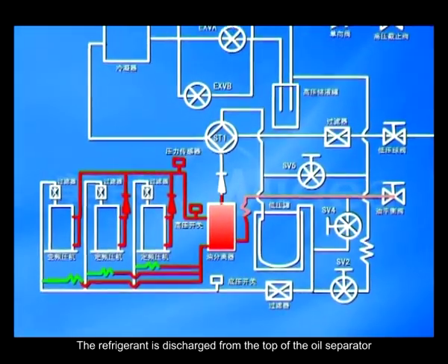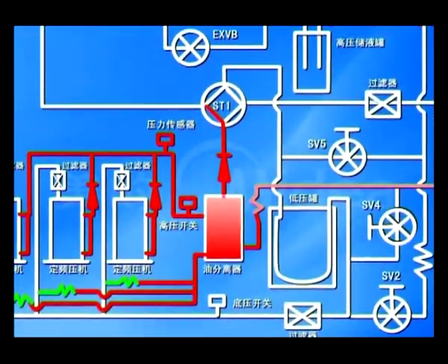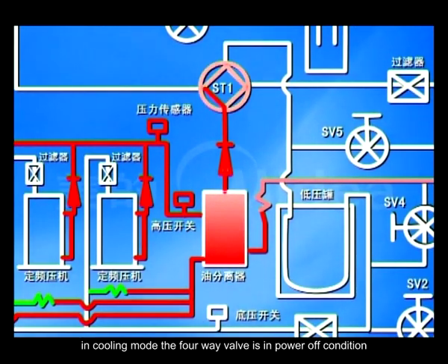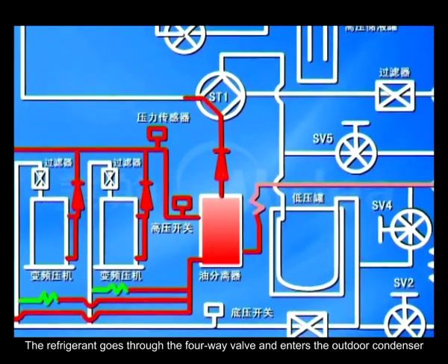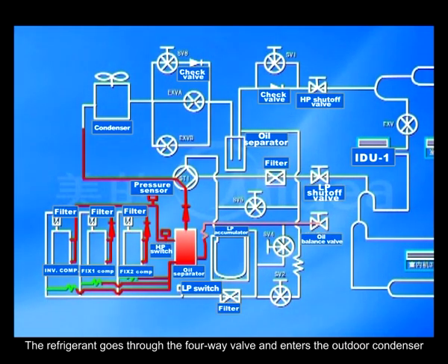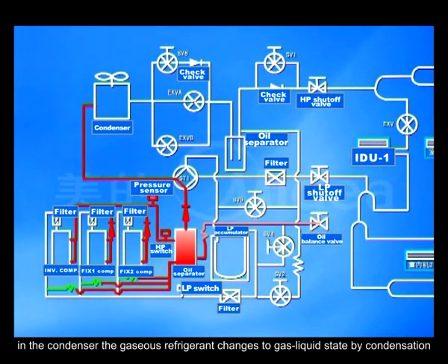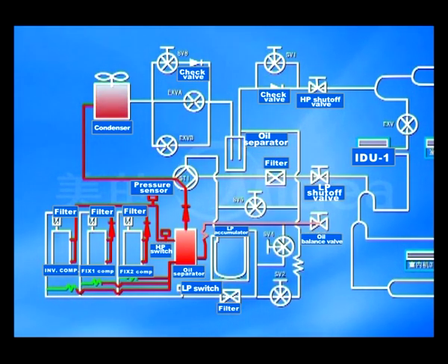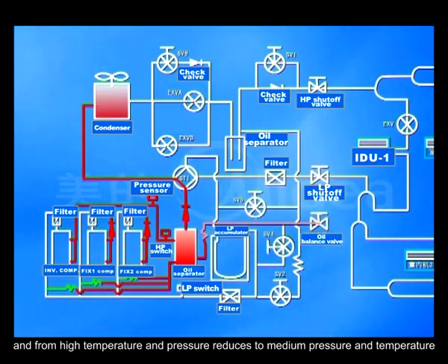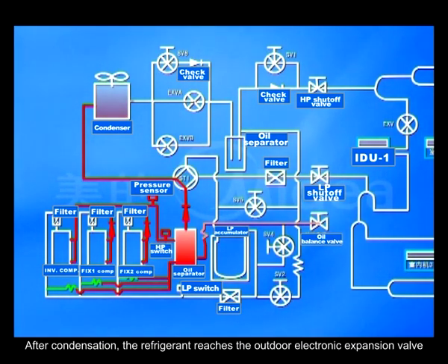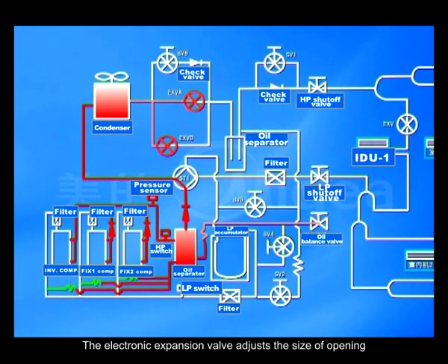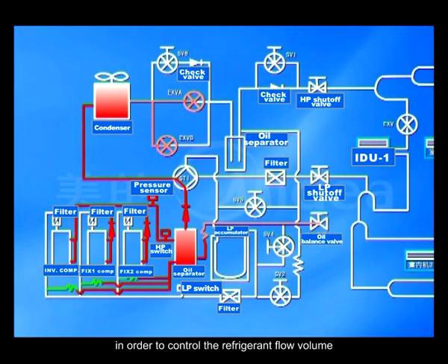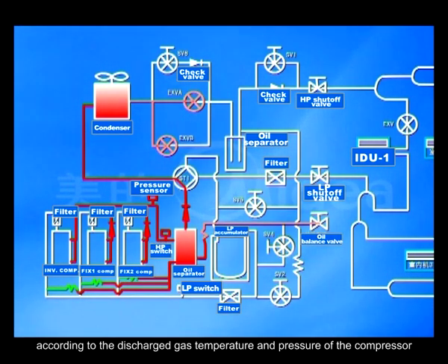The refrigerant is discharged from the top of the oil separator, then enters the 4-way valve. In cooling mode, the 4-way valve is in power-off condition. The refrigerant goes through the 4-way valve and enters the outdoor condenser. In the condenser, the gaseous refrigerant changes to gas-liquid state by condensation, and from high temperature and pressure reduces to medium pressure and temperature. After condensation, the refrigerant reaches the outdoor electronic expansion valve. The electronic expansion valve adjusts the size of opening in order to control the refrigerant flow volume according to the discharged gas temperature and pressure of the compressor.